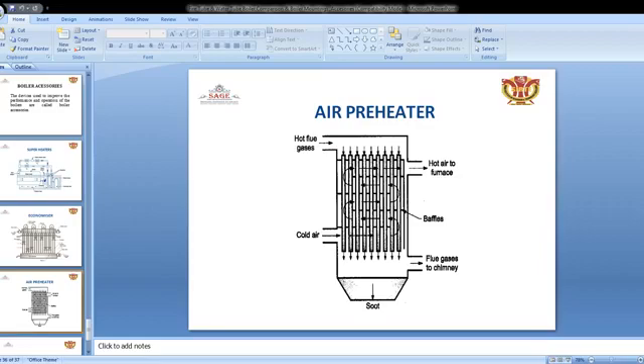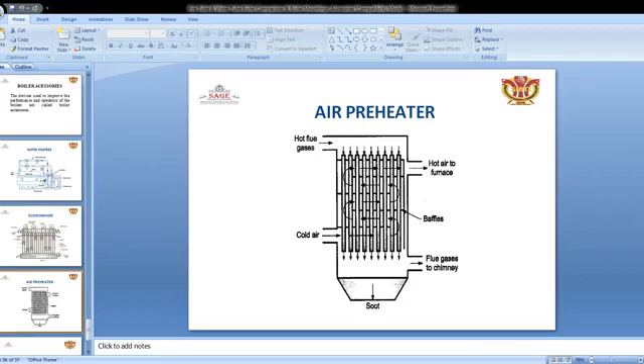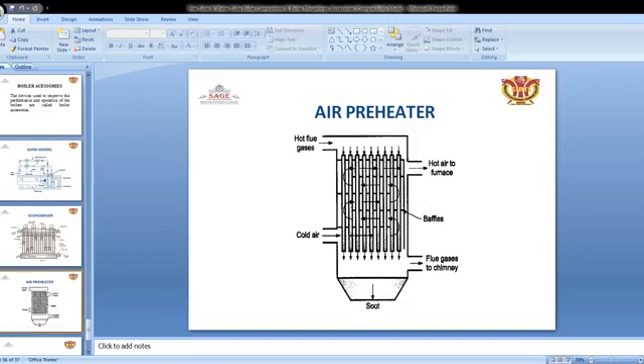The air preheater supplies preheated air into the boiler for combustion of fuel. The air is preheated by the hot flue gases which would otherwise escape through the chimney. The advantage of the air preheater is that fuel requirements are lower. Hot flue gases pass through one side, and hot air is supplied to the furnace, while cold air enters from the other side and flue gases exit to the chimney.